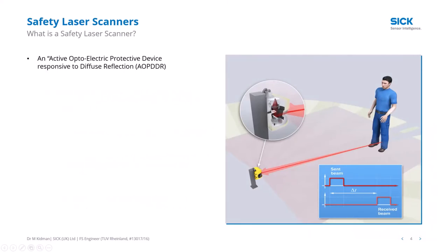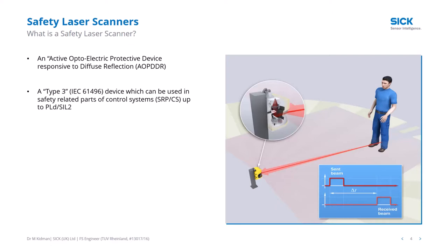Safety laser technology is described as an active optoelectronic protective device responsive to diffuse reflections. A transmitter sends out a pulse of light, it hits an object and returns, and based on the speed of light we calculate how far away the object is. It's a Type 3 device, usable in safety-related control systems up to PL d / SIL 2, constructed according to IEC 61496. If you need PL e / SIL 3, you'd use an alternative such as a safety light curtain, which can be Type 4 (enabling PL e / SIL 3) or Type 2 (enabling PL c / SIL 1).